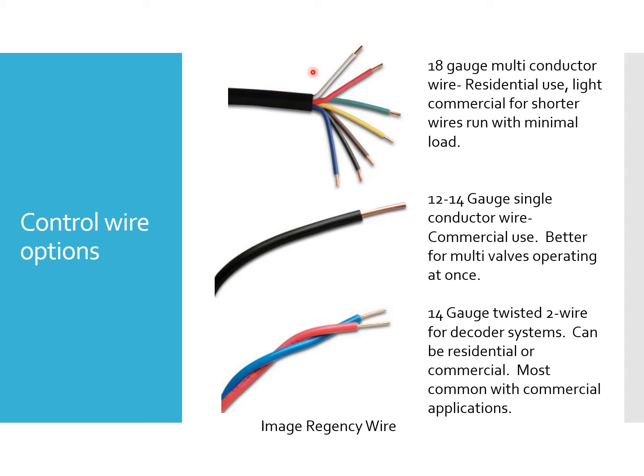So when you have 18 gauge wire, it's pretty small. So remember, the larger the number, the smaller the wire. And because this is 7 conductor, what that means is you can operate up to 6 valves with it. So however many conductors it is, you subtract 1 for the common wire, and then all the rest can be for individual valves. I'm pointing towards the white wire for the common wire because that's the industry standard. Other than that, that wire is no different than the rest of them.